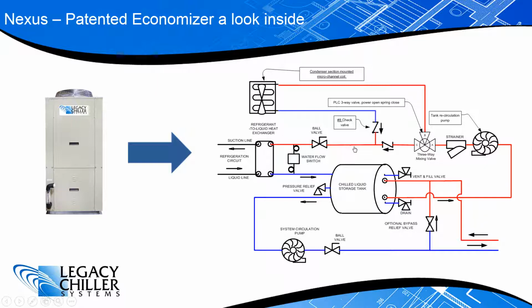All right. So what will happen is the PLC will run in this mode when you have a call for cooling, and what the PLC is looking for is progress at dropping this tank temperature. The current software says that I need to be able to drop the tank temperature 1 degree Fahrenheit for every 180 seconds of operation, right? So if it's making progress, then it's going to stay in economizer mode, and the mechanical mode is going to stay off. So at any time, though, if the economizer cannot keep up, the PLC will automatically switch this back from A to C and put it in mechanical mode, start the compressor, and finish out the call cycle in mechanical cooling, right? So that's kind of how that works.